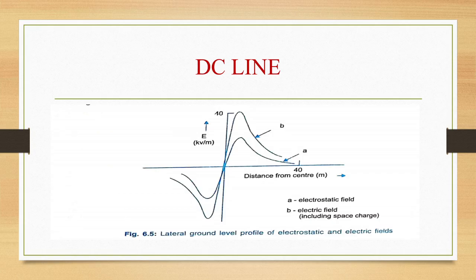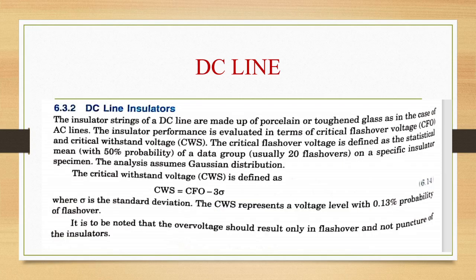The computation of ion flow fields is complex as nonlinear partial differential equations are involved. Computations are simplified by Deutsch's major assumption that the space charge affects only the magnitude and not the direction of the electric field. This reduces the two-dimensional ion field problem to a one-dimensional problem. Recent research efforts are directed at improving the accuracy of computations without Deutsch's assumption, thus allowing the consideration of the effects of wind velocity.